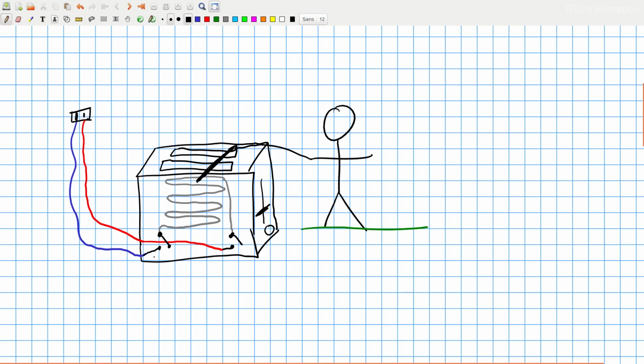This is why you don't want a cord or outlet that's wired backwards. If you want to check an outlet in your house to see if it's wired backwards, it's very easy. Get a multimeter, set it to AC volts, and measure between the neutral and the ground — you should get something very close to zero. Then measure between the ground and the live — you should get approximately whatever your mains voltage is in your country. If you get the opposite, your outlet is wired backwards, and you should get an electrician or fix it yourself, because that can be quite dangerous.